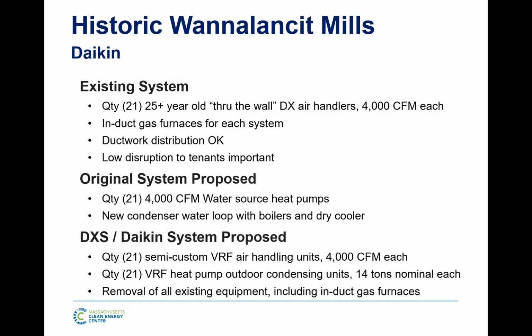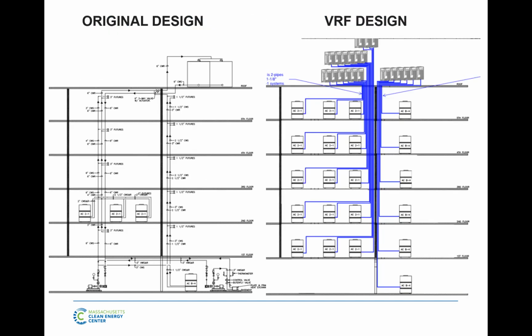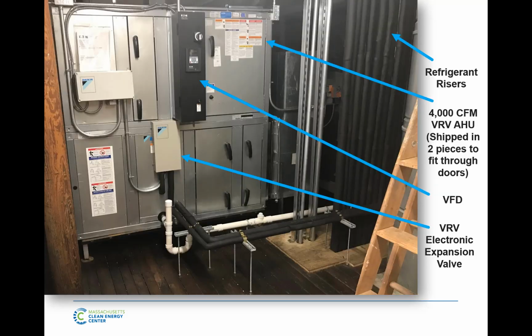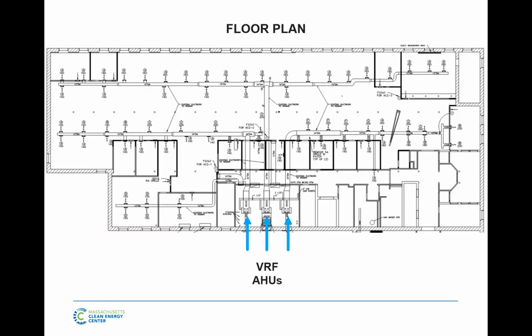They had old 10-ton through-the-wall units. So this is a special VRF system in that there are no regular VRF fan coils in here. So I'm going to skip to the pictures because it'll keep it much quicker and simpler. So, here's the floor plan. They had a little mechanical room with 3 big 10-ton machines with all this duct work going out. And we did all this retrofit work without disturbing any of the tenants. All we did is we ripped out these units and replaced them with 3 12-ton or 10-ton VRF air handlers.